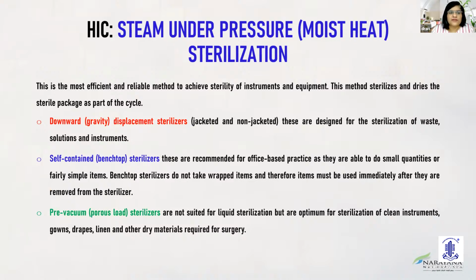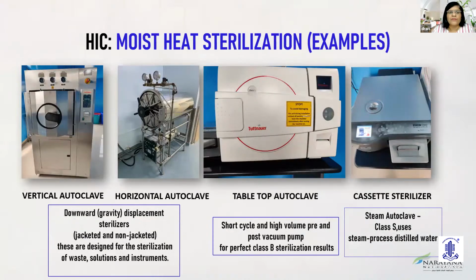You can have three types of sterilizers: the gravity displacement type sterilizers, the self-contained sterilizers, and the pre-vacuum porous load sterilizers. All these sterilizers have different qualities, and they are designed for the sterilization of waste, solutions and instruments. The benchtop sterilizers are recommended for office-based practice as they are able to handle small quantities of fairly simple items. Pre-vacuum or porous load sterilizers are not suited for liquid sterilization, but are optimum for sterilization of clean instruments, gowns, drapes, linen, and other dry materials required for surgery.